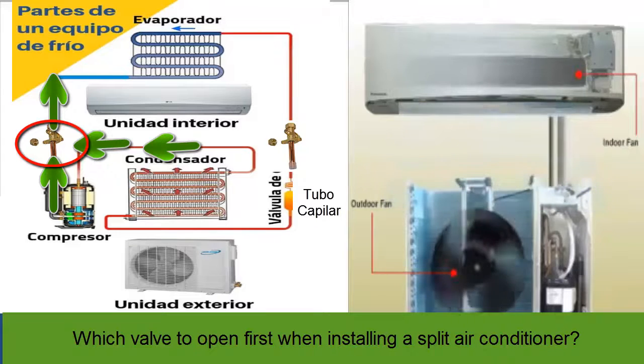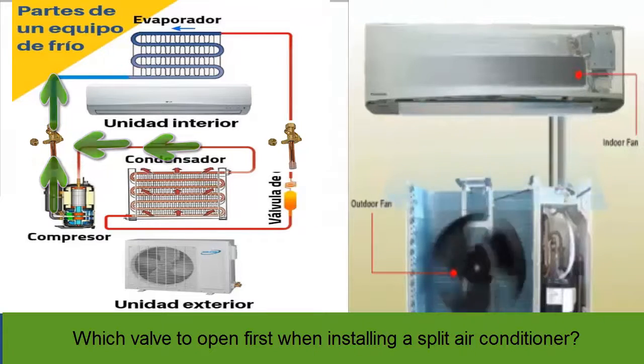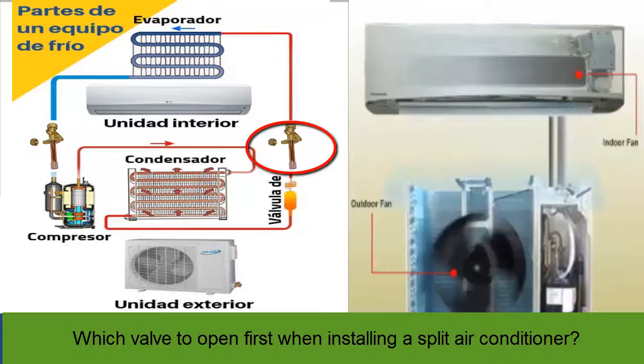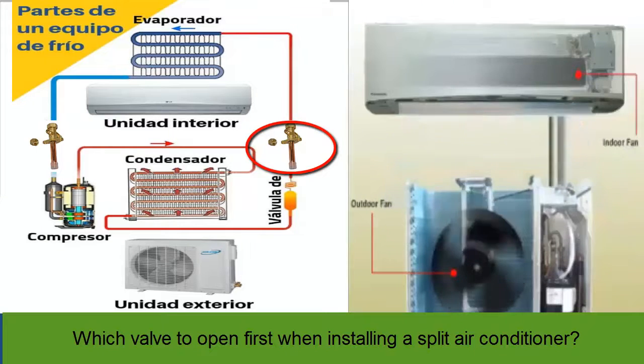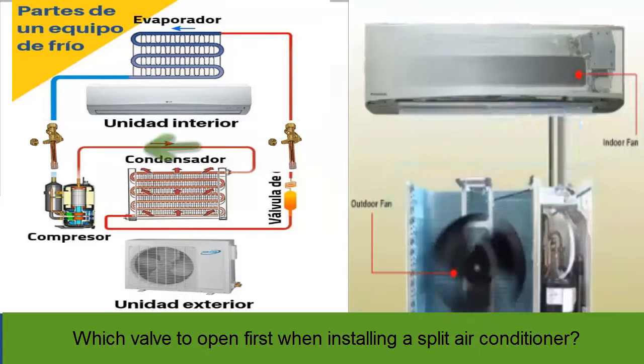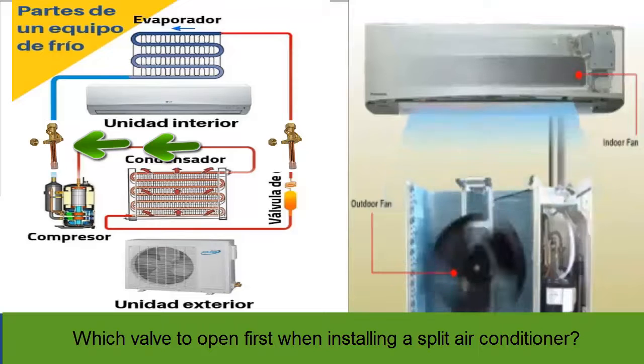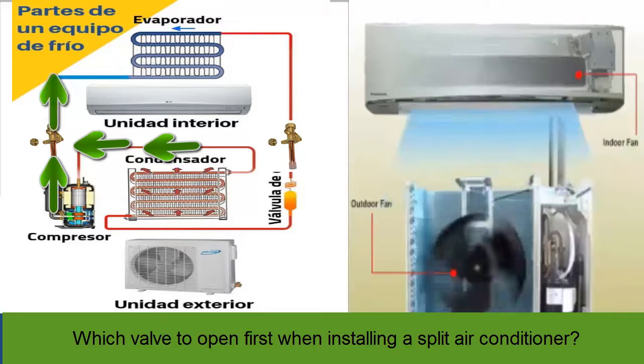This prevents the loss of compressor oil to the discharge line and out of the liquid line. While it is unlikely that enough oil will be lost to cause immediate damage by slowly opening the liquid line, any oil the compressor loses has a long way to go before returning to it. The loss of oil in those first moments of a new system's life can have lasting effects on the operation and longevity of the compressor.